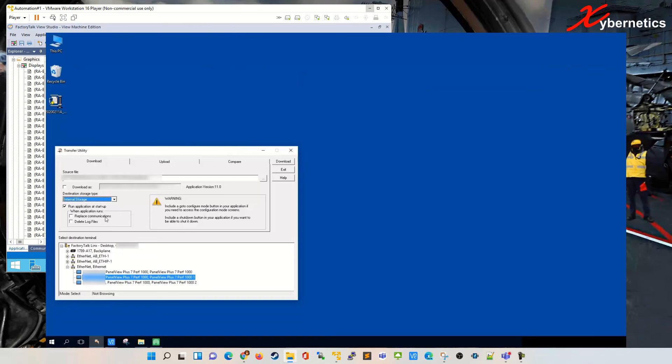If you put a check here, you replace your RSLinx Enterprise communication. To delete the log file, you put a check here to delete all your log files. Log files pertain to trending, so you will lose all the trending in this process. Just be aware when you delete the log file.